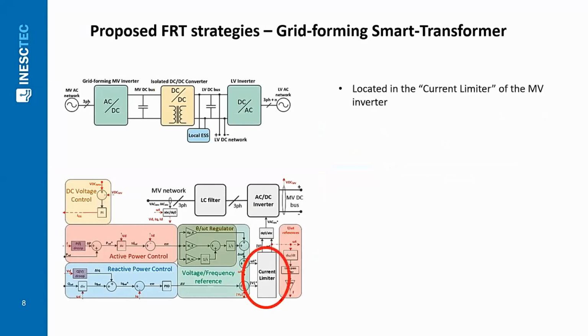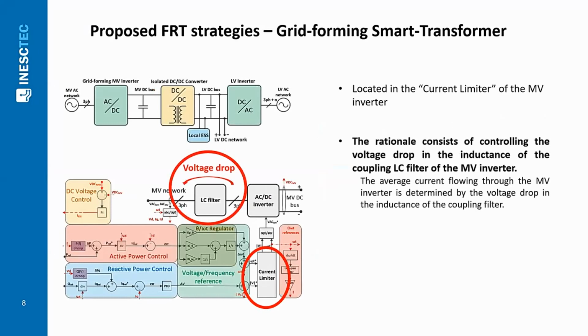The fault ride-through strategy for the grid-forming smart transformer is based on a different approach. It is located in the control structure of the medium voltage inverter, namely in the current limiter block. The rationale consists of controlling the voltage drop in the inductance of the coupling LC filter of the medium voltage inverter. It exploits the fact that the current of the medium voltage inverter is determined by the voltage drop in the inductance of the coupling filter. Since the grid-forming smart transformer has a local energy storage system, it relies on it to assure the power balance in the smart transformer. There is no need for direct intervention on it to provide fault ride-through.